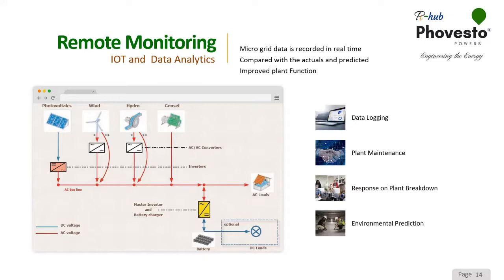First, take the solar photovoltaic mode. If a customer installs a 1 kilowatt system on the solar plant, it's directly converted from DC to AC and goes directly to the loads. If there is no battery, first priority is set to that — it goes directly to the load. This is called direct feed mode. Otherwise, it goes to charge the batteries.